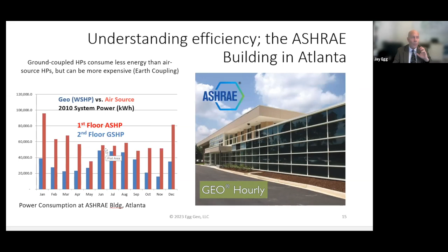So what does that mean in the big picture? If your electric grid is used to handling summer peaks, it's also going to be able to handle the winter peak for the same building if you're using a geothermal solution. But if you're using an air source solution, the grid isn't going to be able to handle it. It's going to crash the grid, kind of like we've heard stories of rolling blackouts and difficulties when we have cold snaps in Texas and other places. That's exactly what's going to happen.